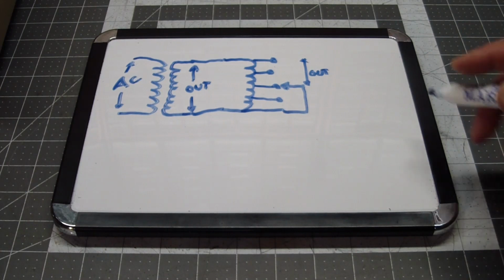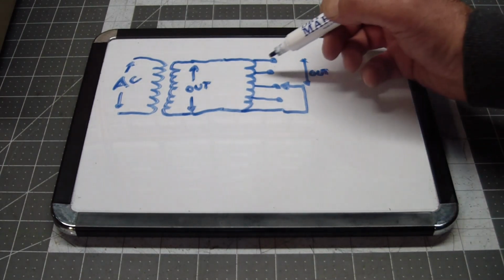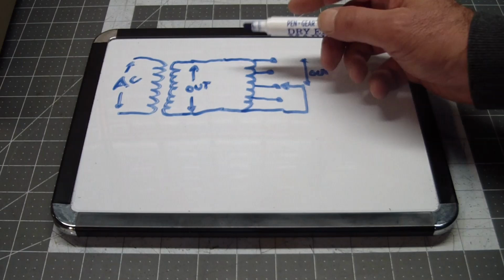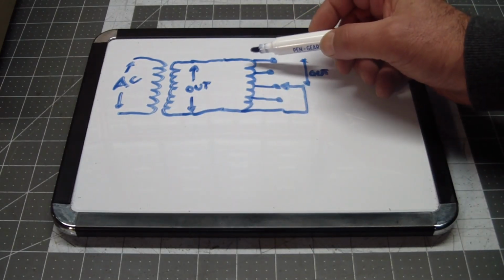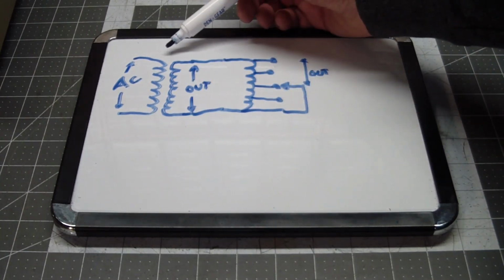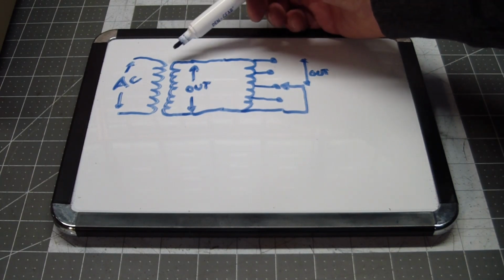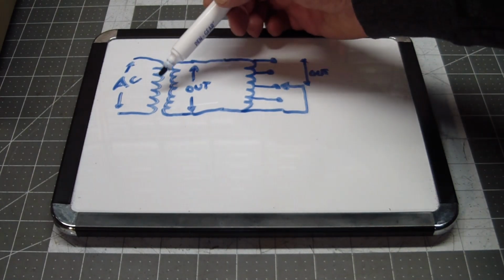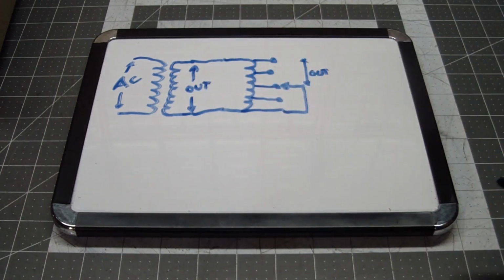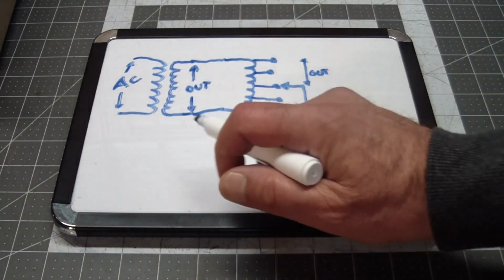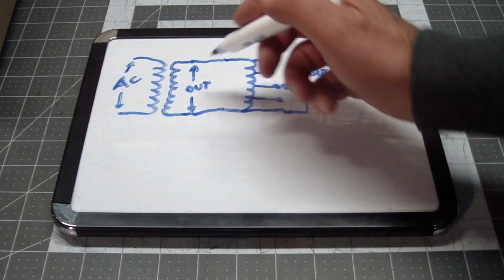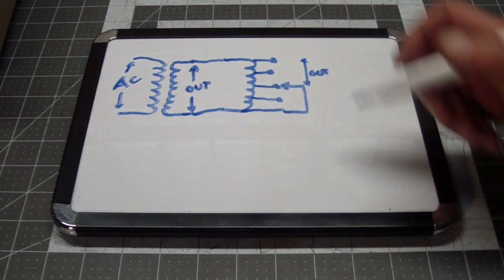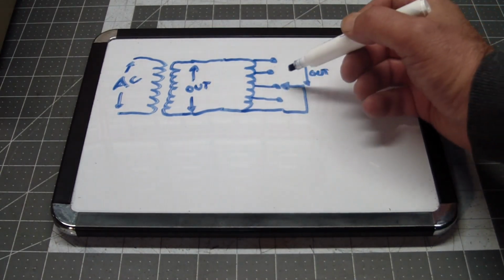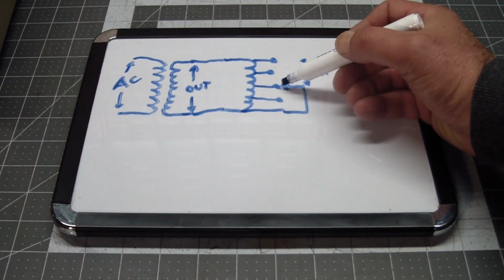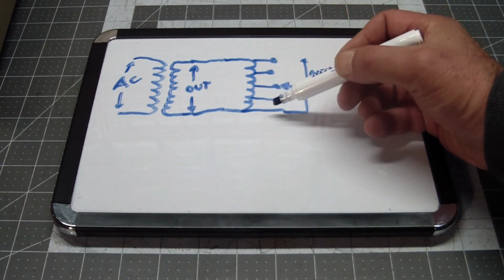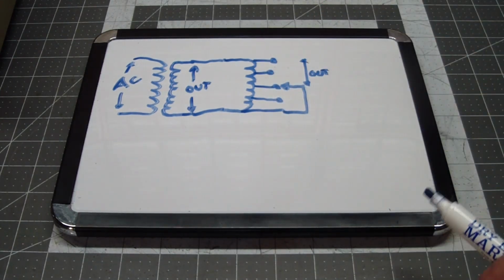So the way these transformers work is, picture this being the windings. Whereas in the primary transformer, I'm sure you've seen it inside, it's got insulated copper wire. The windings are on top of each other, touching each other, but because they're insulated, there's no shorts, so it doesn't matter. However, in this case, we have to actually make an electrical connection to somewhere on the primary winding in order to affect the output voltage.